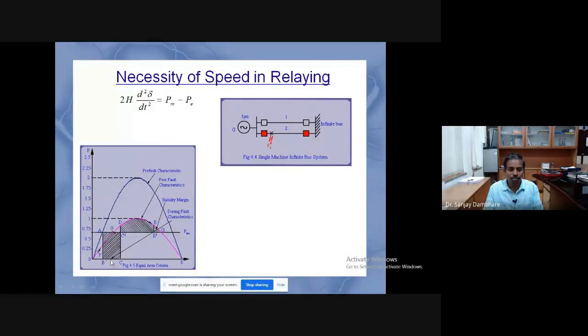So you move from point B to C, and somewhere you have to open this faulty transmission line. If you open this faulty transmission line, then the power flow will shift from this curve to this curve. This is the power flow P-delta curve with both the lines. This is the P-delta curve with the single line, and that's why in this period the generators are accelerating, and in this period the generators are decelerating, and this acceleration and deceleration is area A1 and area A2.